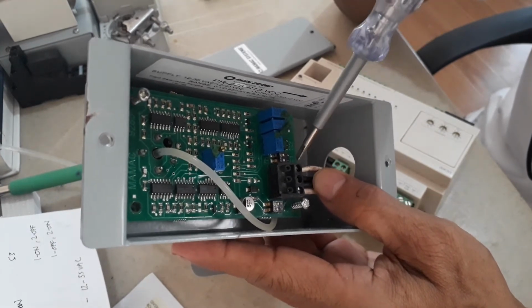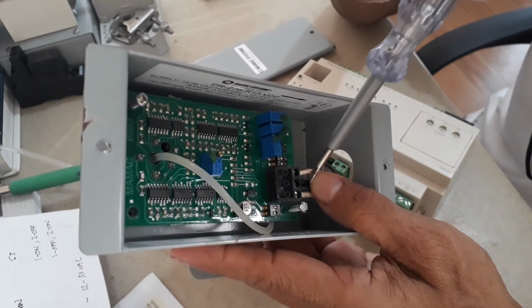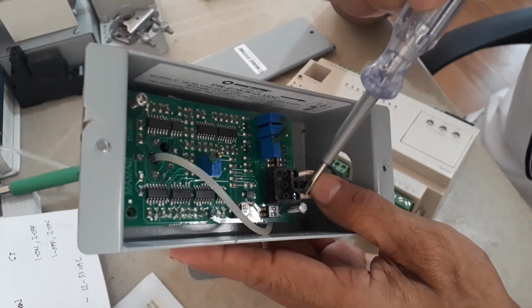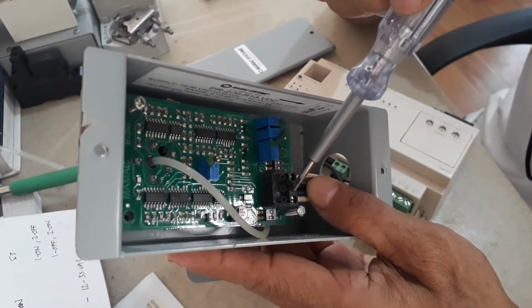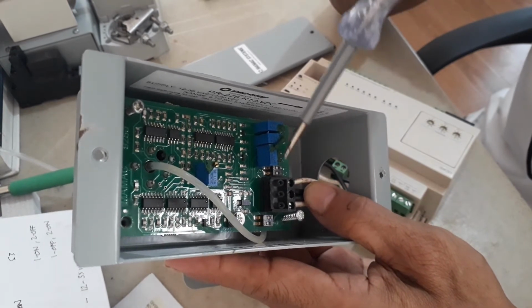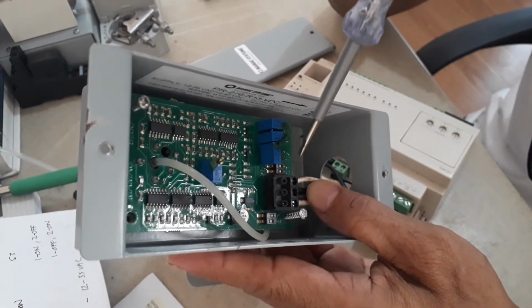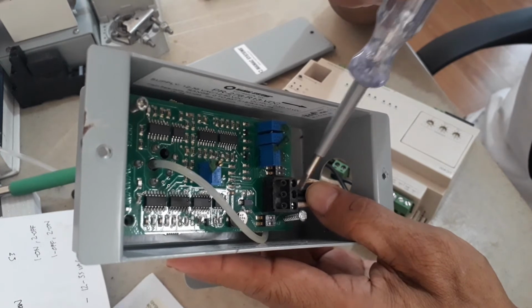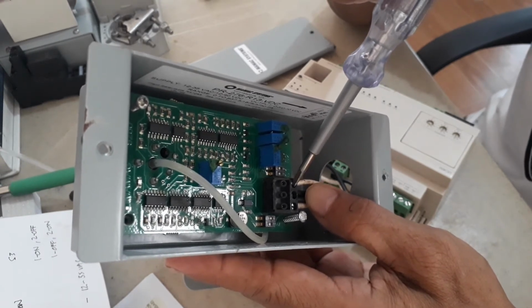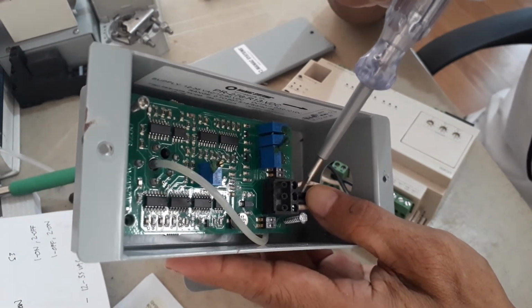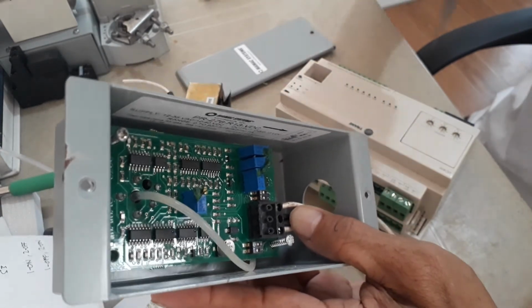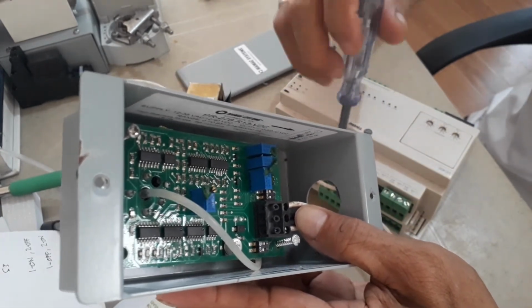Okay, as you can see here, there are 3 terminals. Now, this is the common. So, power supply, 24 volts, then common of the power supply. Then the control output or the signal output is this. This is the 0 to 10 volts. Then this is the common. They are sharing the common. Okay. So I have shown you already how it will be terminated in the DDC.